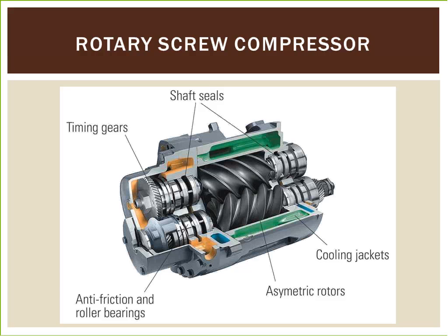For the latter control technique, a slide valve is positioned in the casing. As the compressor capacity is reduced, the slide valve opens, bypassing a portion of the compressed air back to the suction. Advantages of the rotary screw compressor include smooth, pulse-free air output in a compact size with high output volume over a long life.